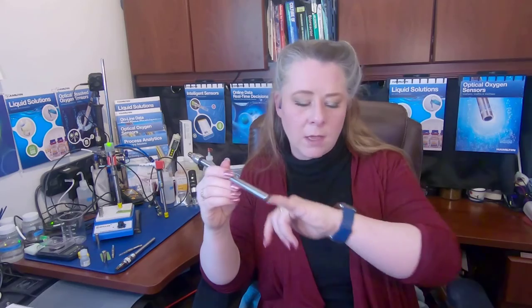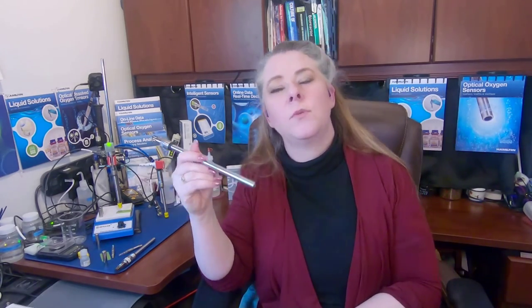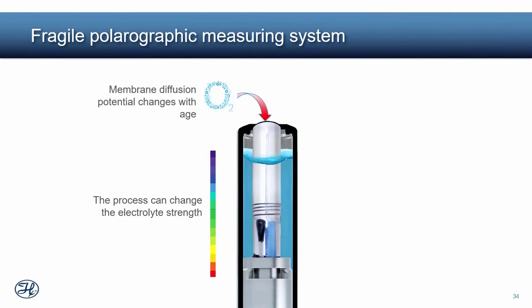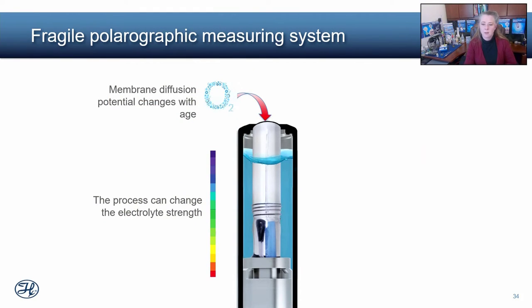Normally, if you saw a lower voltage reading, you would think that means less oxygen. But if you were never measuring oxygen at all and you just change the pH of that electrolyte, it will also read a lower voltage. And that's not due to reduced oxygen, it's due to a change in the probe, which means these sensors over time will start to artificially read lower oxygen, even if you maintain consistent oxygen levels. So that's something to think about, because your process itself affects the probe.